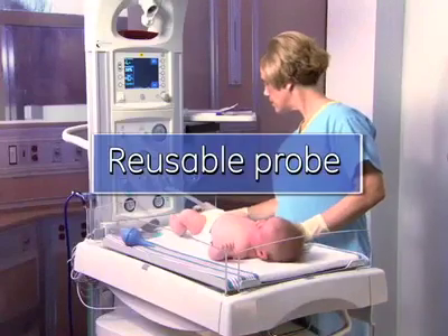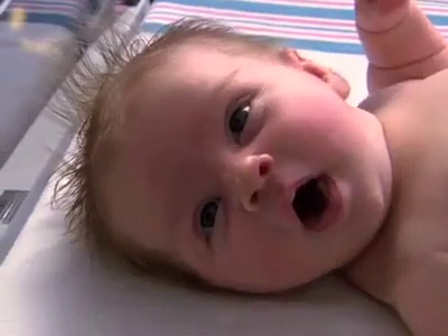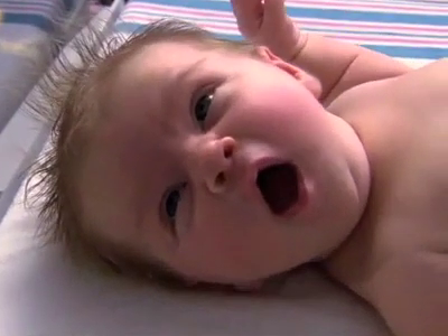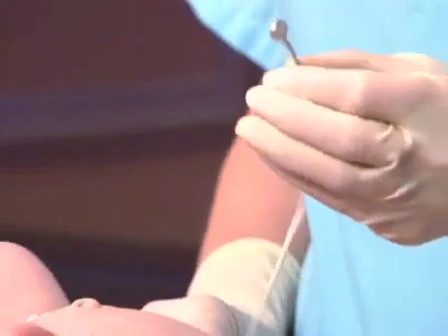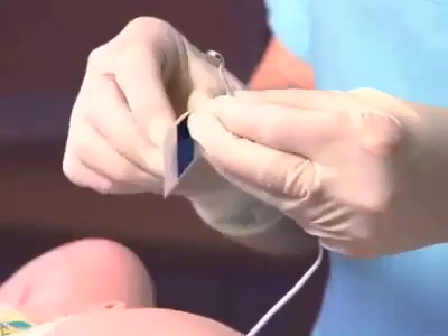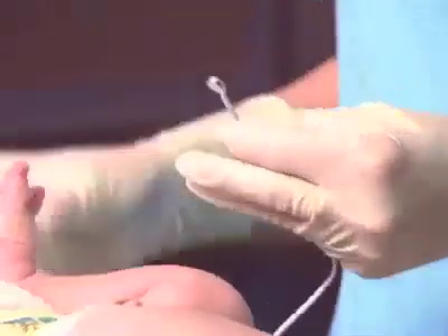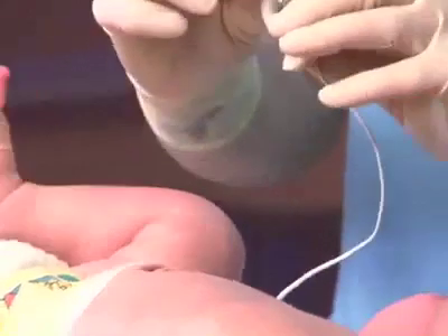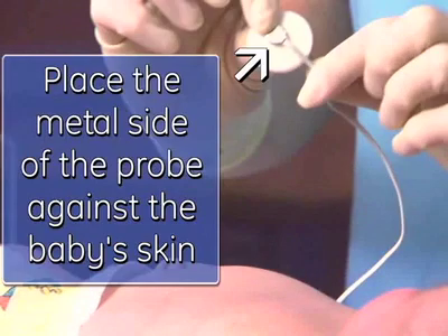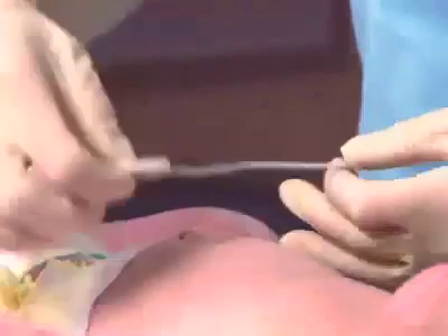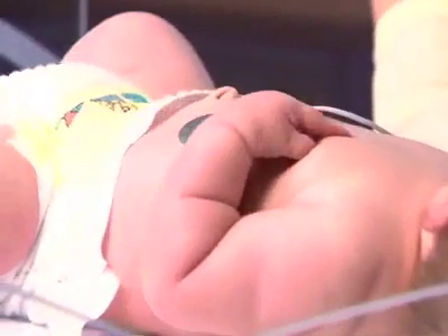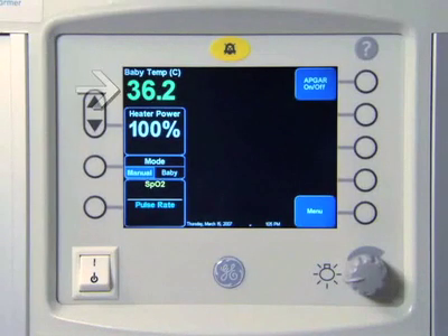To attach the reusable probe, use a heat-reflecting patch. Peel the paper backing from the adhesive side of the patch and place the patch over the probe with the reflective foil side up. Place the metal side of the probe against the baby's skin at a site consistent with your unit's policy and procedures. The probe must be directly in the path of the radiant heat. The baby's temperature will be displayed in green above the power setting.